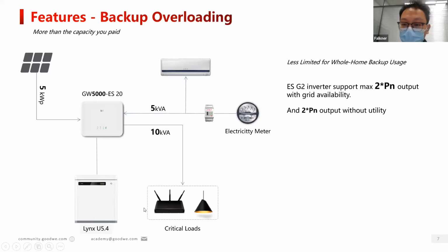ES G2 inverter supports maximum 2 times PN power output with the grid availability, or even without the grid. As you can see, our output is 10 kilowatt. For the critical loads, this is very helpful for the heavy loads.